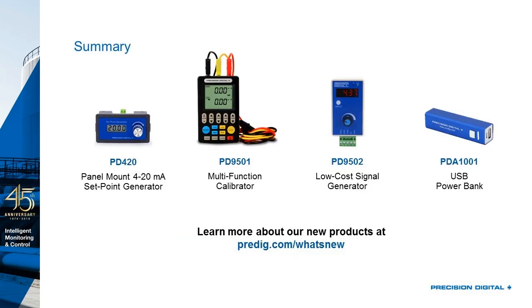So what have we seen here today? Well, we saw our PD420 panel mount 4 to 20 milliamp set point generator, manually controlling 4 to 20 just by turning that knob. We also saw our PD9501 multifunction calibrator, a great way to get precise signals in and out, measuring and sourcing for just about any kind of process signal you're going to work with.